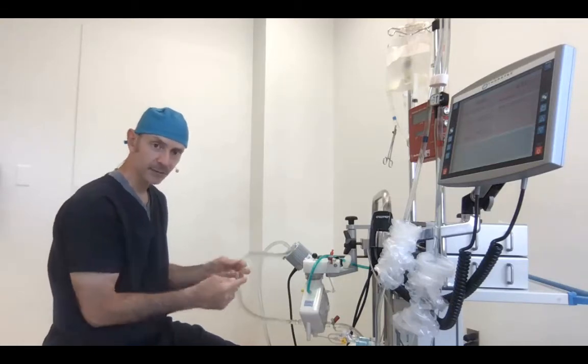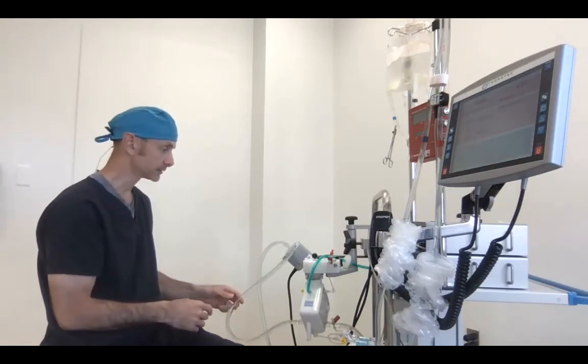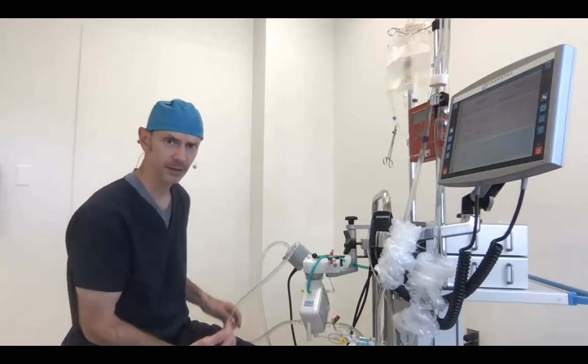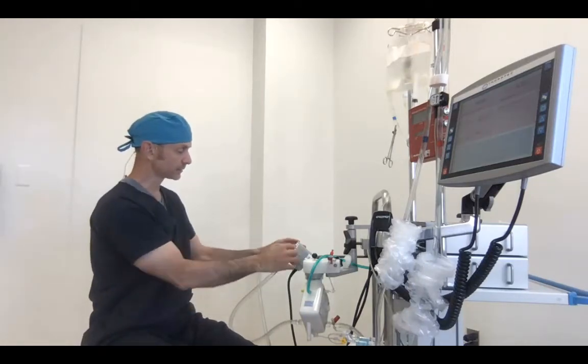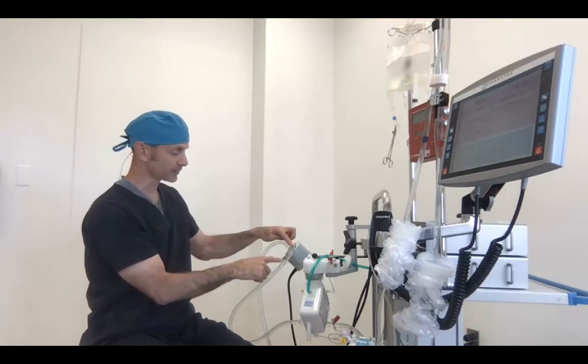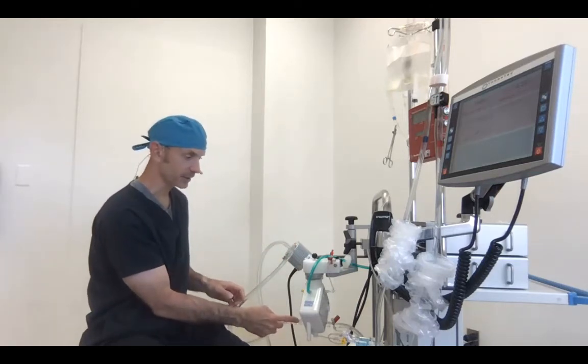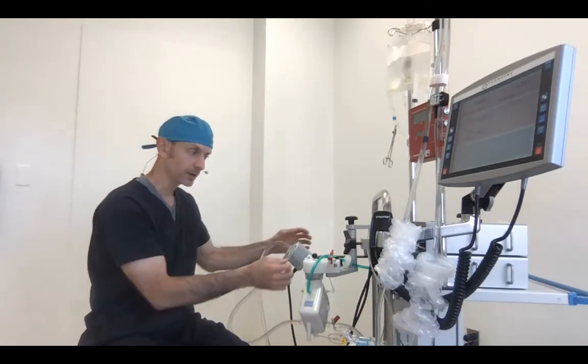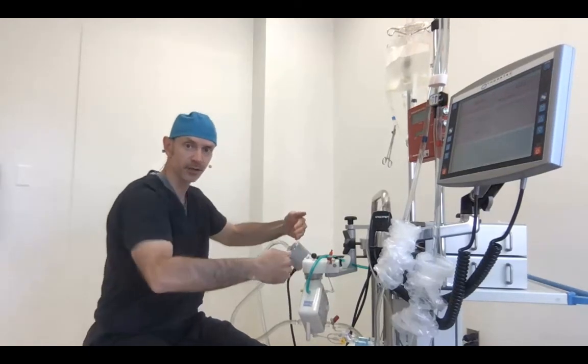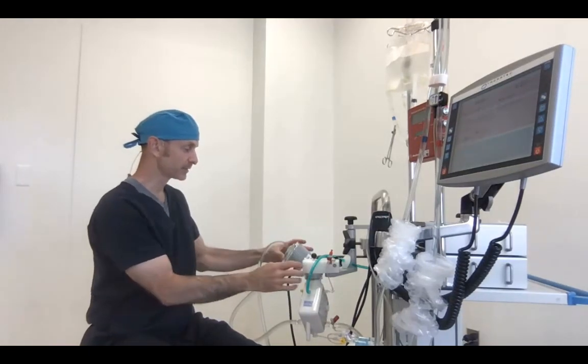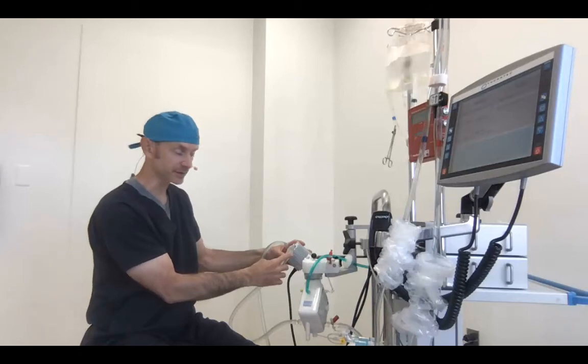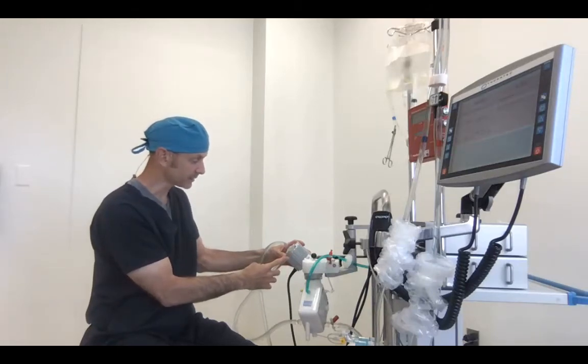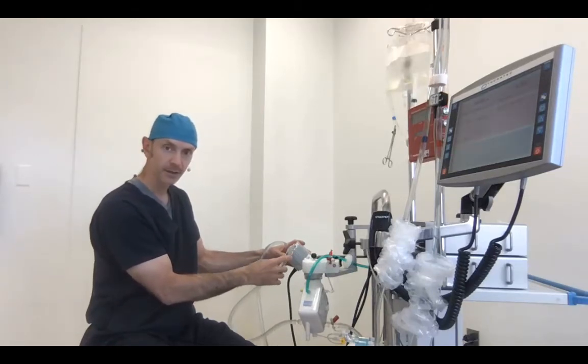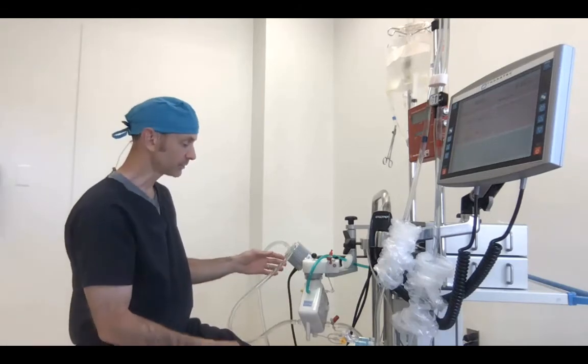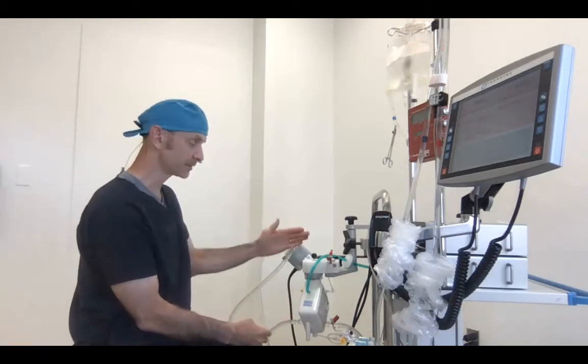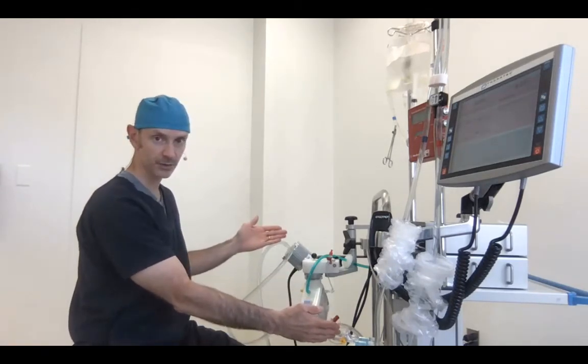So what happens if we kink this line? And how could you possibly kink that line? Here's how you could kink that line. Look, the outlet of the pump is here, and the inlet of the oxygenator is there. And if you go out on a transport and you're holding this cart next to a patient's bed, things start to bump up against each other, and these brackets shift, and maybe this line gets kinked like that. So what does it look like when you have high resistance in between the two sources that you can monitor?